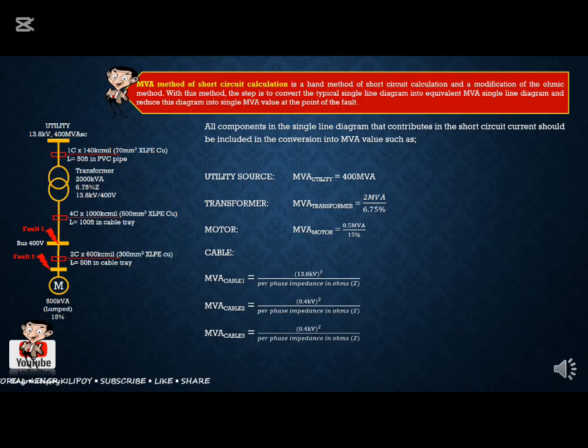For cable 3, 400 volts bus, since this is the bus on the MCC, motor control center. So lump means pinagsama-sama na natin lahat yung motor load. So meron siyang 500 kVA. So for the cables of 600 kcmil, which has 2 cores per phase and length of 50 feet, i-convert natin yan to per phase impedance.